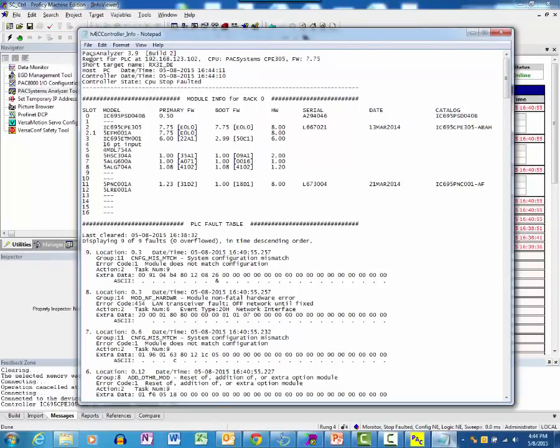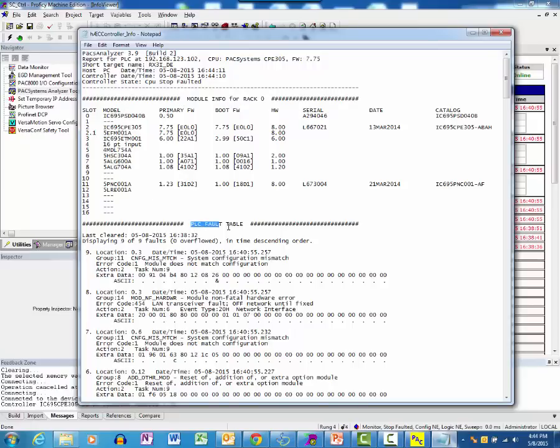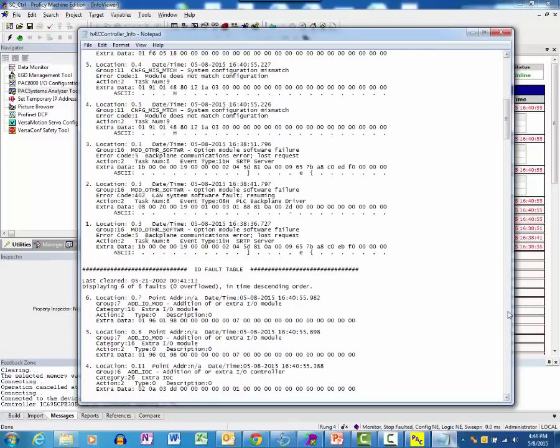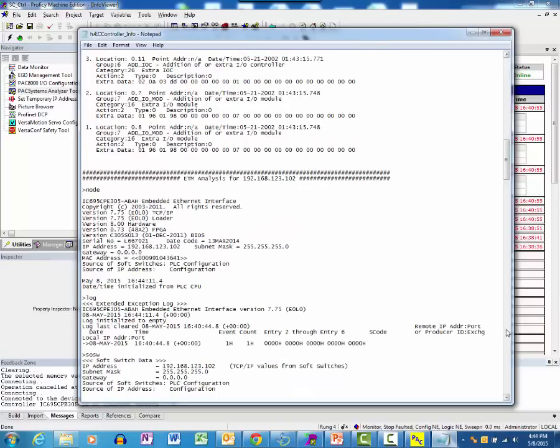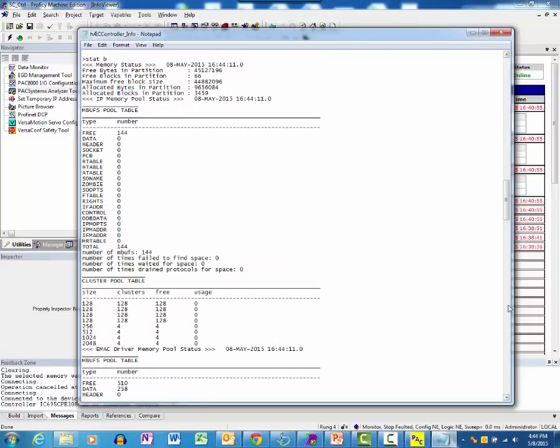Observe the contents of the report. All the module information for Rack0 is summarized first. The PLC fault table with all its details is listed next. Scrolling down, we see the IO fault table contents. Scrolling down further, we see the Ethernet module detailed analysis for the controller.